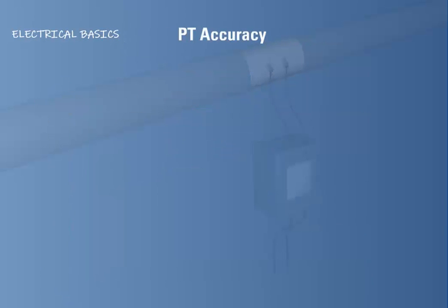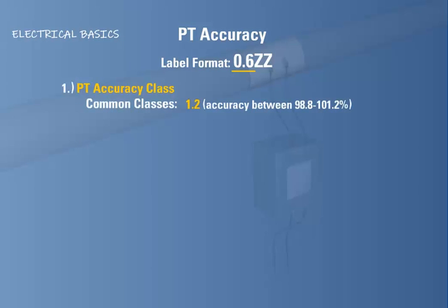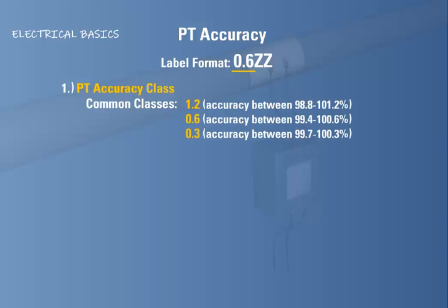The accuracy of a PT's operation is specified in the displayed label format. The first item in the label indicates the accuracy class of the PT. The three common accuracy classes are: 1.2, indicating PT accuracy between 98.8 and 101.2%; 0.6, indicating PT accuracy between 99.4 and 100.6%; and 0.3, indicating PT accuracy between 99.7 and 100.3%.